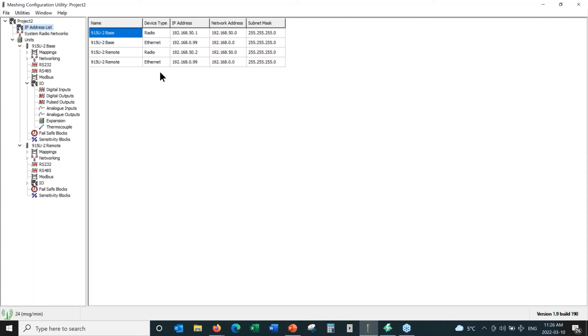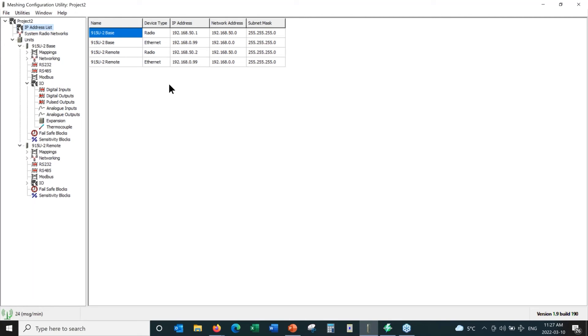The Ethernet port can never be connected to the radio port, and that was done for security reasons — so that if somebody obtained access to the Ethernet port of one radio, they wouldn't be able to log into a remote radio and change its configuration over the air. It is possible to set these radios up for over-the-air configuration, but only from one master base radio, for security reasons. You don't want someone at a remote site breaking into an electrical cabinet and changing parameters on other radios. That's why we can have all Ethernet ports with the same address — you drive to a remote site, no guessing the IP address, it's the same at all remote sites.